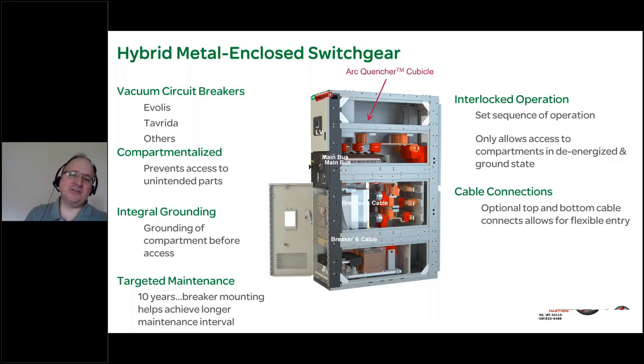In terms of the construction of this hybrid metal enclosed switchgear, you can see that similar to metal clad, again, borrowing some of those design features, it's a highly compartmentalized design. Typically in our design, we have the arc quencher located in the top cubicle. The breaker, and this is strictly a one high design, so two high is not available in this design. And the targeted maintenance for the circuit breakers here is 10 years for either the Evolis or the Tavrida circuit breaker. The switch, the isolation switch, is electrically interlocked with that circuit breaker.